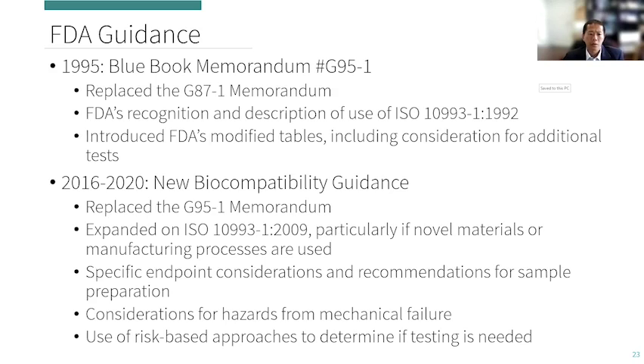We also talk about use of specific endpoints and recommendations for how samples should be provided. I think what's also unique to the FDA guidance document is providing considerations for hazards from mechanical failure. So these would include failures and potential failures such as coating delamination, which could then potentially leach out chemicals.